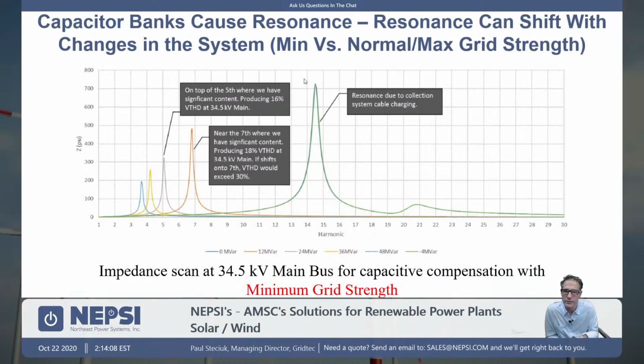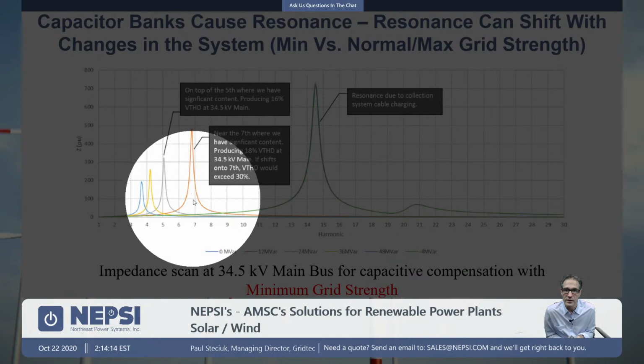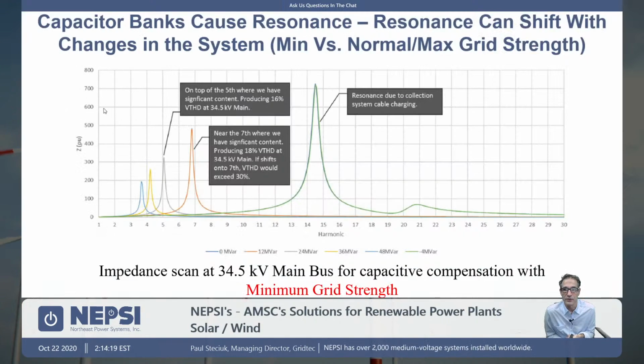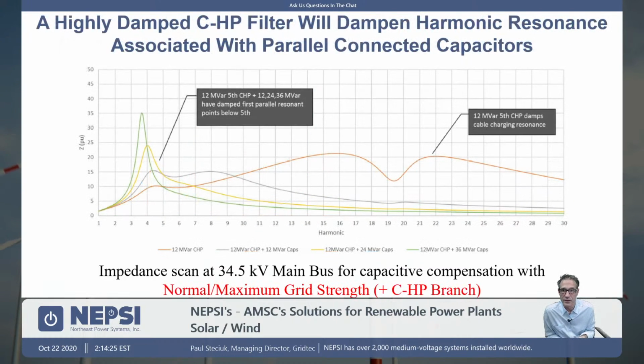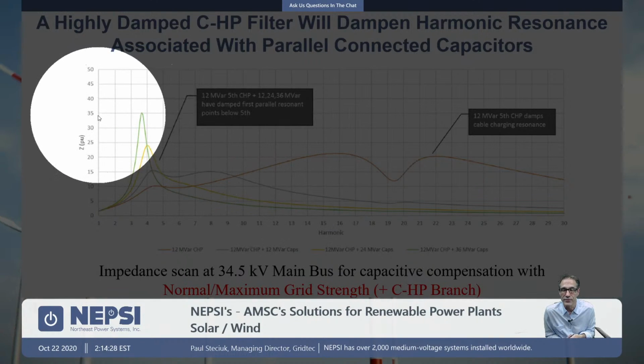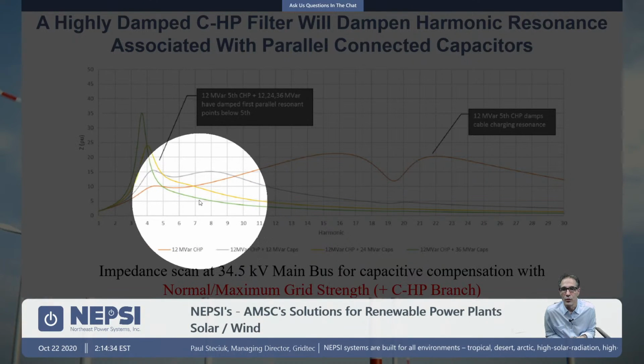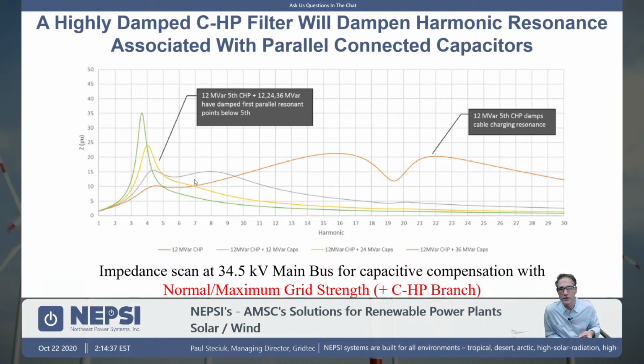So what this means, remember, I think we've talked about in other tech talks, is that if we have harmonic current injection at these various harmonics, the current times that impedance gives you the per unit voltage. Okay, so here you can see that there's a magnification concept because of resonance. Putting that C high pass filter in, we basically dropped that per unit impedance to a maximum of 35. Okay, so it's a very interesting thing here. One C high pass filter, 3 capacitor stages, and we reduced the magnitude of the worst case resonant condition to 35 per unit for the impedance. And that's an interesting concept.